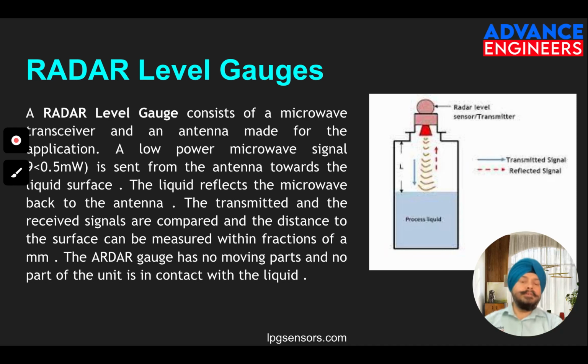Radar level gauges will give you an accuracy of 1 mm. That is the highest accuracy available as of now for instrumentation. And radar gauges don't have any moving parts - no pulleys, no motors, no gearboxes, no float, nothing. So they are relatively better placed in today's technology compared to servo gauges for installation.